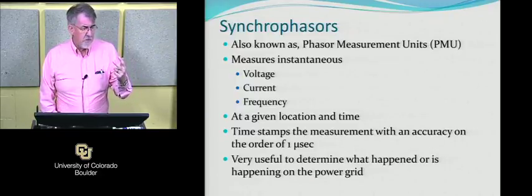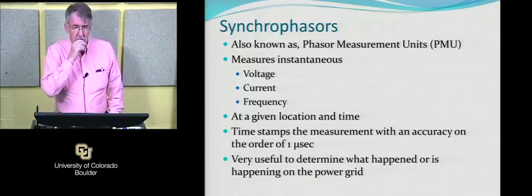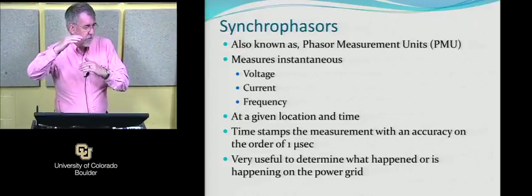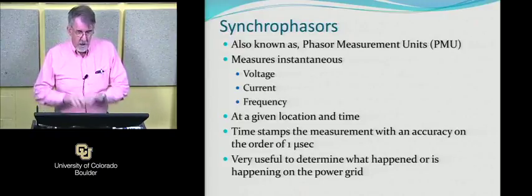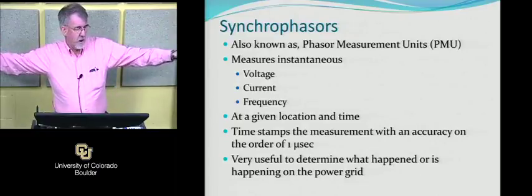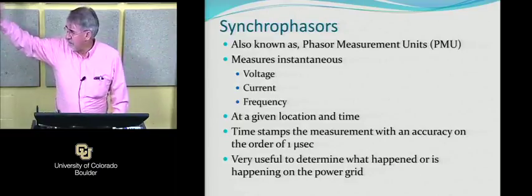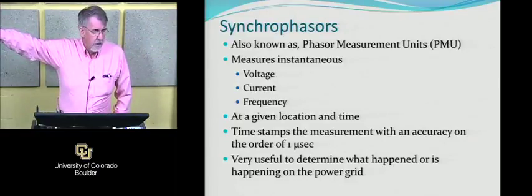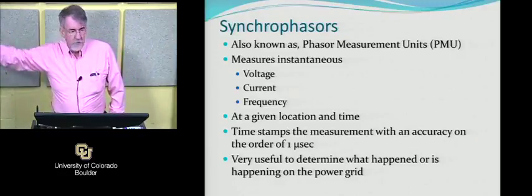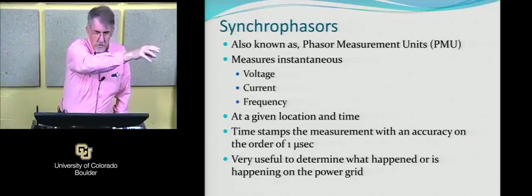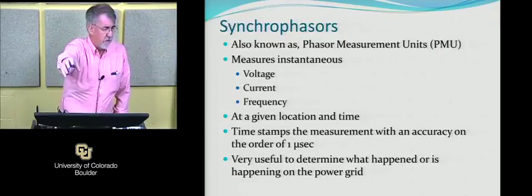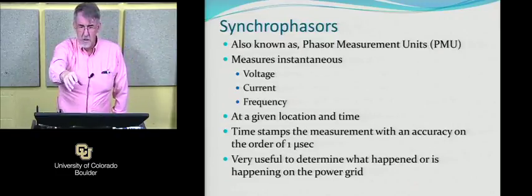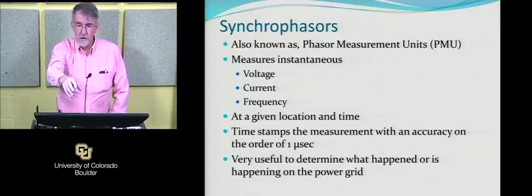So the operators tend to watch it and operate within limits that say, for instance, I've got all these transmission lines, this one's carrying 50 megawatts. If it suddenly went down and I had to move that 50 megawatts to other lines, do I have enough capacity on all the other lines to absorb it without getting a cascading failure?